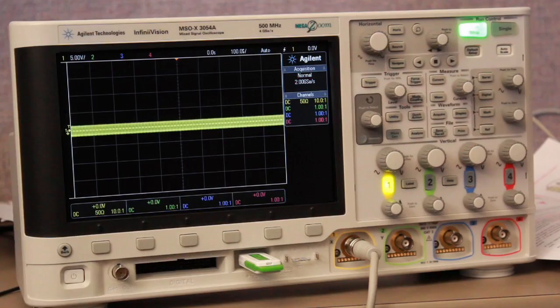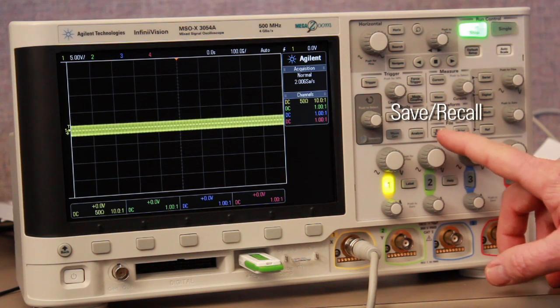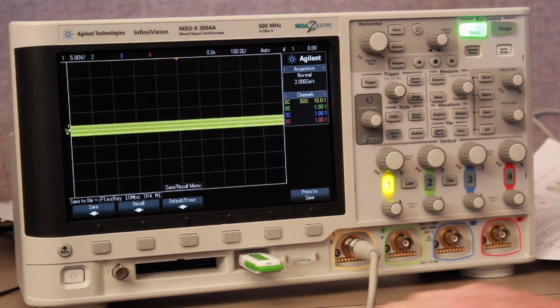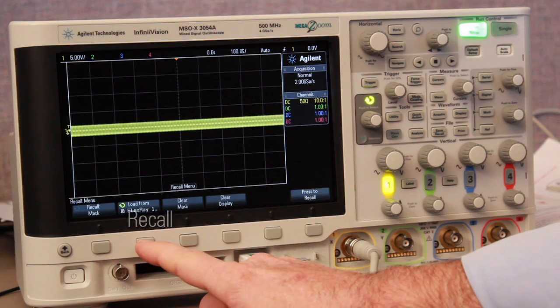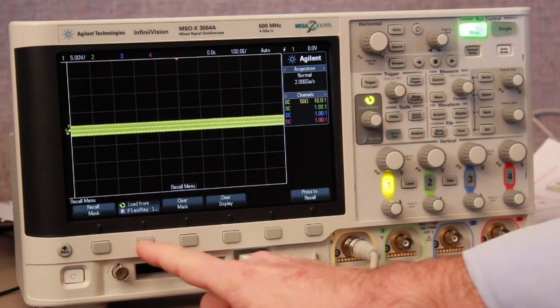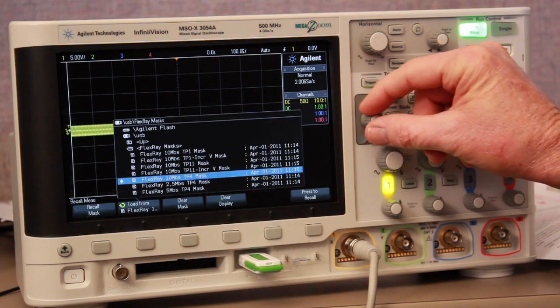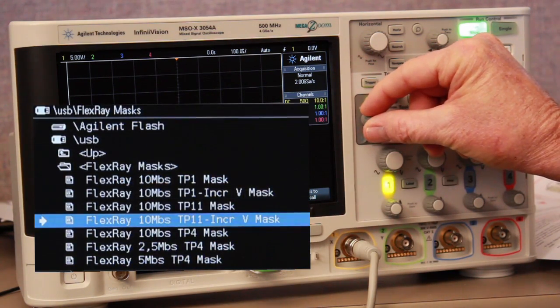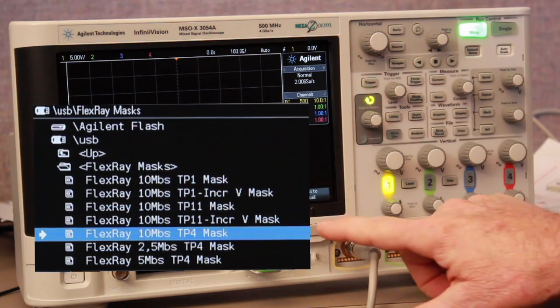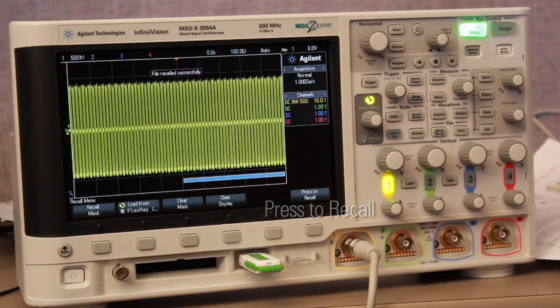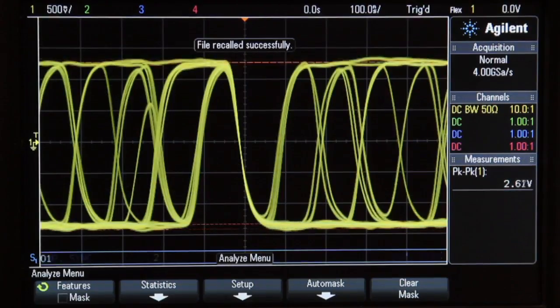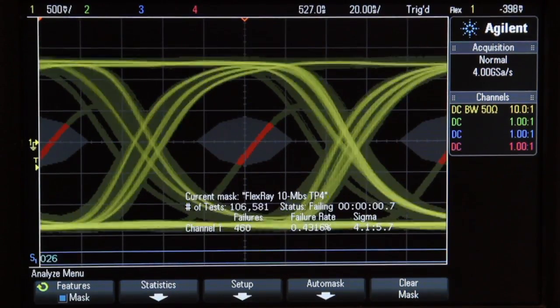Let's now make a FlexRay eye-diagram mask test. Begin by pressing the Save/Recall front panel key. Next, select Recall, then navigate to the appropriate mask file. In this case, I'm going to recall a 10 Mbit per second TP4 mask file, which is used for testing all signals at the input of a FlexRay receiver.